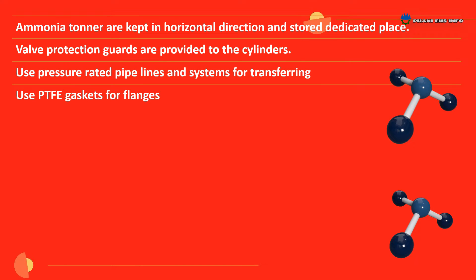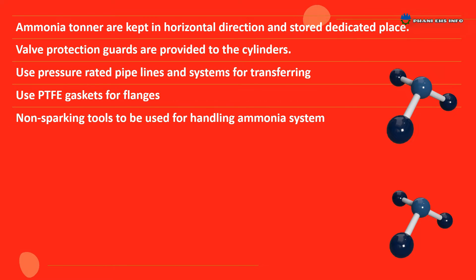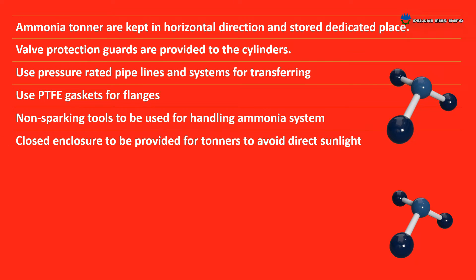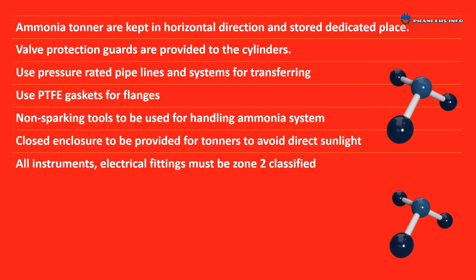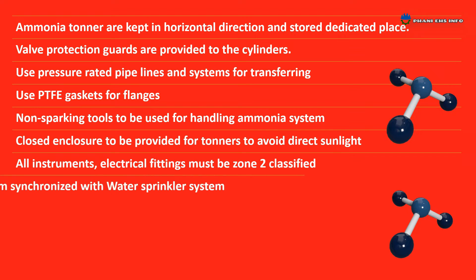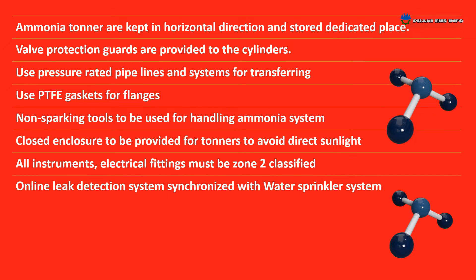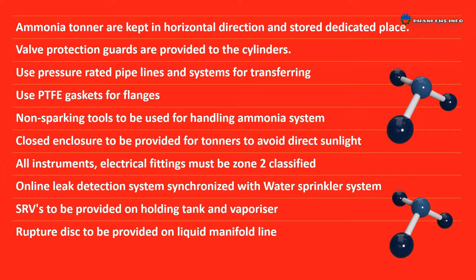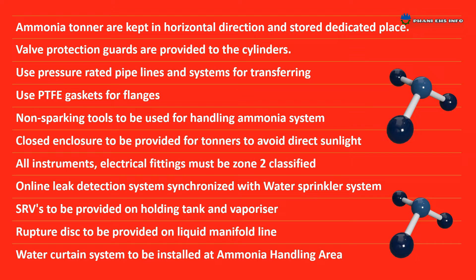Use PTFE gaskets for flanges. Non-sparking tools are to be used for handling ammonia systems. Closed enclosure to be provided for tonners to avoid direct sunlight. All instruments and electrical fittings must be zone-classified. Online leak detection system synchronized with water sprinkler system. SRVs to be provided on holding tank and vaporizer. Rupture disc to be provided on liquid manifold line. Water curtain system to be installed at ammonia handling area.